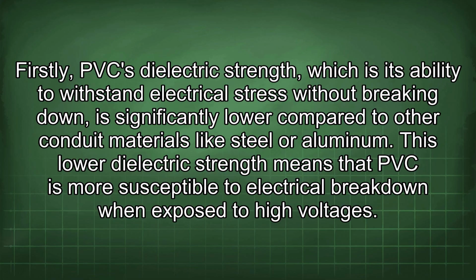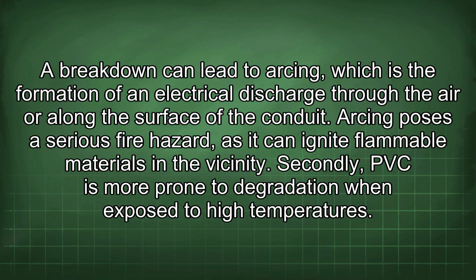This lower dielectric strength means that PVC is more susceptible to electrical breakdown when exposed to high voltages. A breakdown can lead to arcing, which is the formation of an electrical discharge through the air or along the surface of the conduit. Arcing poses a serious fire hazard, as it can ignite flammable materials in the vicinity.